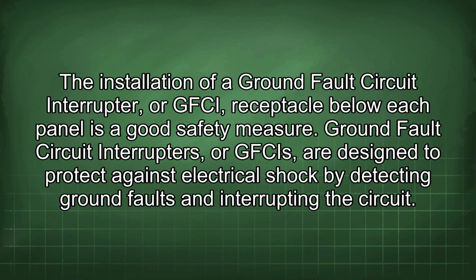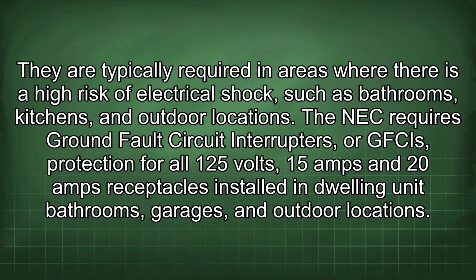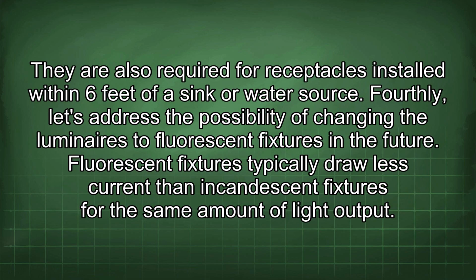lighting circuits. The installation of a ground fault circuit interrupter, or GFCI, receptacle below each panel is a good safety measure. GFCIs are designed to protect against electrical shock by detecting ground faults and interrupting the circuit. They are typically required in areas where there is a high risk of electrical shock, such as bathrooms, kitchens, and outdoor locations. NEC requires GFCI protection for all 125 volt, 15 amp and 20 amp receptacles installed in dwelling unit bathrooms, garages, and outdoor locations. They are also required for receptacles installed within 6 feet of a sink or water source.